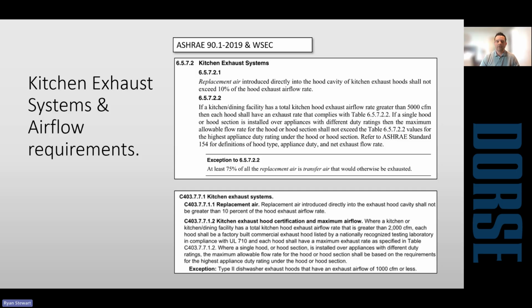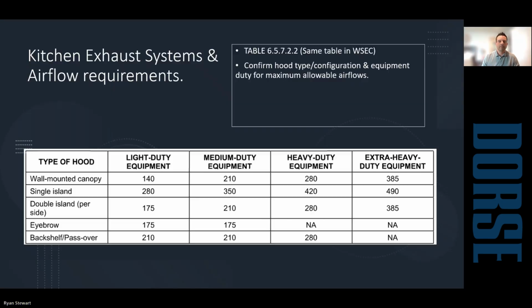And then you need to refer to a table that references by appliance duty what your maximum CFM is for that appliance duty. So you're going to look at the heaviest duty cooking appliance under each hood to determine the duty. So here's an example of that table. You'll find down the left side your different types of hoods, wall canopy, single island, your various types, and then across the top what those appliance duties are. And then it's going to give you a maximum airflow per linear foot for each of those appliance duties and hood type.